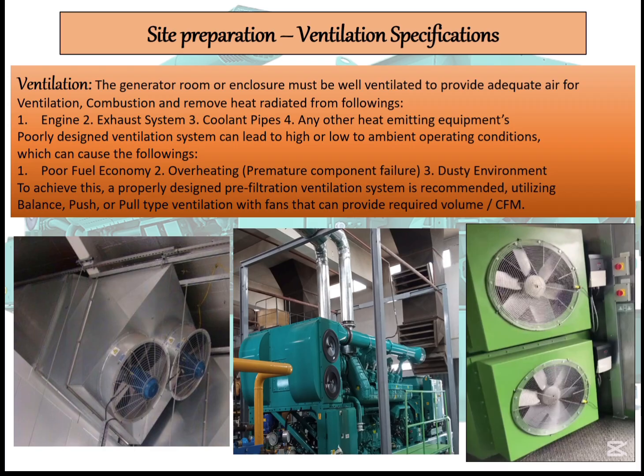We have abstraction only, where we just put the fans on the extractor side that can also suction air from one side of the enclosure and just pass the hot air outside, something like the diesel radiators that are mounted with the generators. They are just suction and throwing the hot air outside. So we can adopt any of the procedures, but the necessity is the air should be clean and dust free, because the air will take part in combustion and cooling.